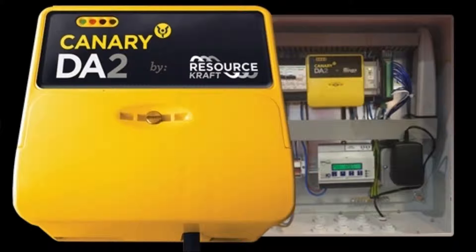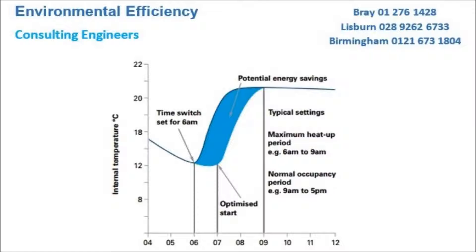Such recommendations would include room thermostats, time clocks, occupancy detectors, weather compensation of heating circuits and data acquisition and control. A good example of improved controls in commercial applications is the installation of optimum start heating controllers. These will vary the start time of the central heating boilers according to the outside weather conditions.